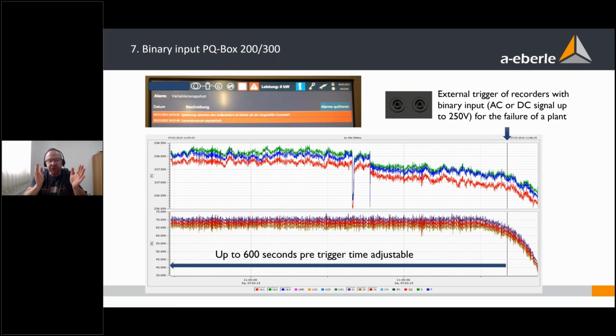And if the machine stops running and you have a problem, you can set up the PQBox so that you have up to 600 seconds pre-time. So in a high resolution, we can look back 600 seconds with the disturbance recorder. What happened? Why did the machine stop?